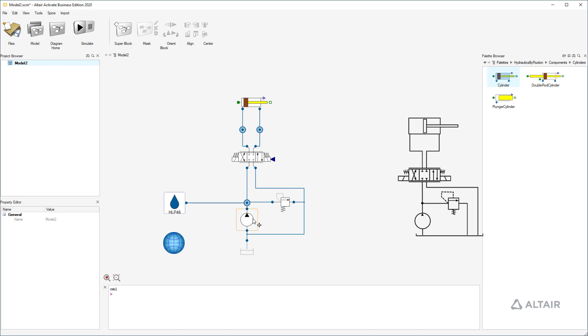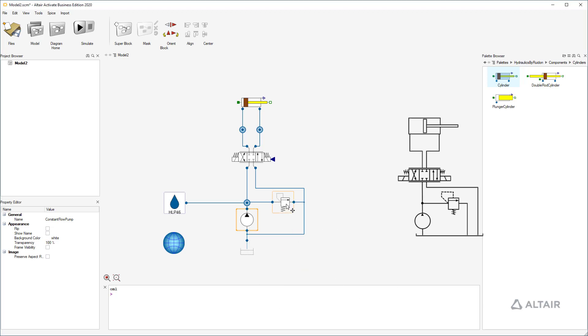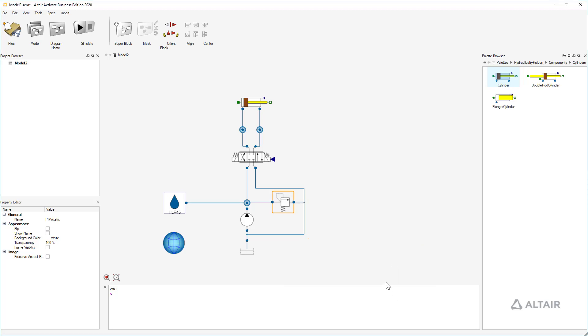After connecting the components we put in some quick parameters. We assume a volume flow of 20 liters per minute and please consider that we have to use SI units. Therefore I am using the conversion factor. A maximum system pressure of 180 bar. As flow rate of the valve we also assume 20 liters per minute at a pressure drop of 5 bar per metering edge.